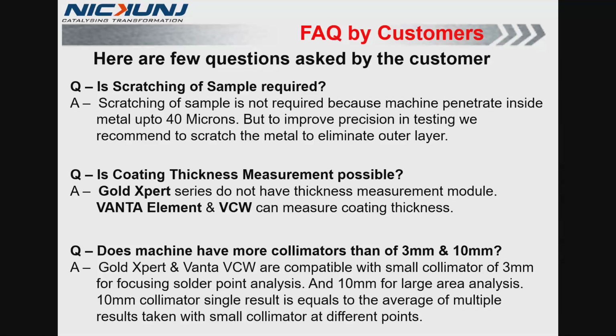Is scratching of sample required? Scratching of sample is not required because machine penetrates inside metal up to 40 micron. But to improve precision in testing, we recommend to scratch the metal to eliminate outer layer. Is coating thickness measurement possible? Gold Xpert series do not have thickness measurement module, but Vanta Element and Vanta VCW can measure coating thickness.